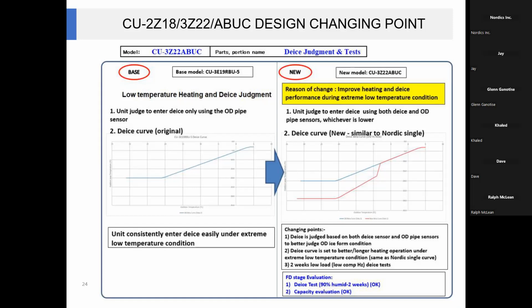So if your customer is saying, oh, my unit goes into defrost every half an hour, you are better off going to the house and proving to your customer that no, it's not possible. Our program is always 60 minutes of full continuous operation before it kicks into a defrost cycle, only if required. Otherwise, you may end up running the whole day with no defrost cycle. It all depends on ambient temperature and refrigerant temperature. As I said before, on the screen on the left-hand side, there was only one sensor monitoring the coil temperature. Now we have 2 sensors, and whichever sensor registers the lower temperature of the refrigerant is going to bring in the defrost cycle.